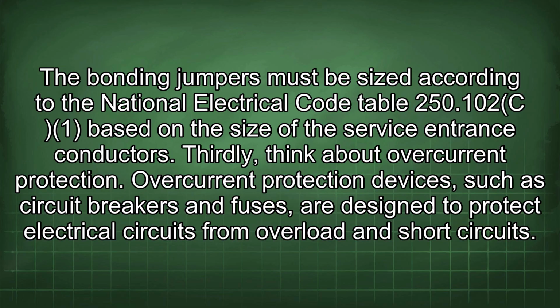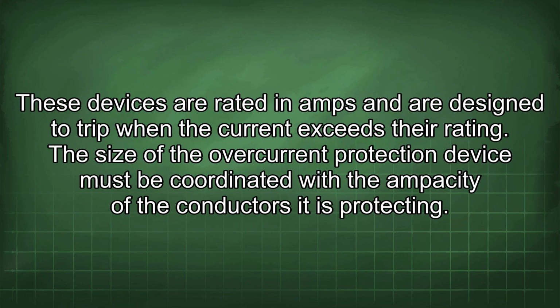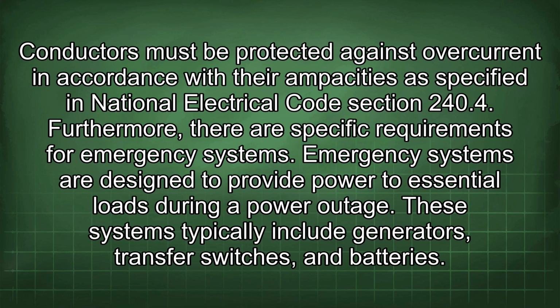Thirdly, think about overcurrent protection. Overcurrent protection devices, such as circuit breakers and fuses, are designed to protect electrical circuits from overload and short circuits. These devices are rated in amps and are designed to trip when the current exceeds their rating. The size of the overcurrent protection device must be coordinated with the ampacity of the conductors it is protecting. Conductors must be protected against overcurrent in accordance with their ampacities as specified in National Electrical Code Section 240.4.